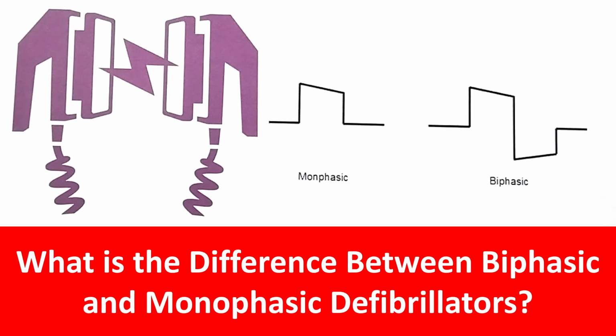Good preparation of the site is also required. If the site does not have good conductivity, that is, if electrolyte jelly is not placed, then there is every chance that skin burns can occur. While applying, you should also give adequate force. The paddle should be pressed on the chest, because defibrillator paddles now sense thoracic impedance, and a green color indication will show that you are pressing properly and the jelly is applied properly. Otherwise, red color might be shown on the paddles.